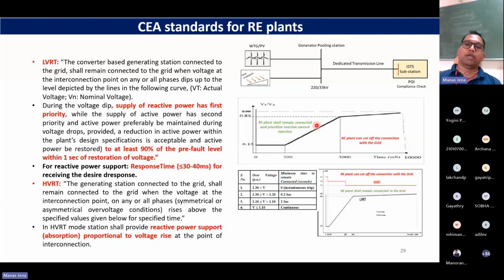you will remain connected. But as an inverter, what will you do? First, because this is a low voltage scenario, you should provide voltage support. That means you have to supply VAR. So the VAR support is given priority during the LVRT. What should be the response time? It should be done within 30 to 40 milliseconds.